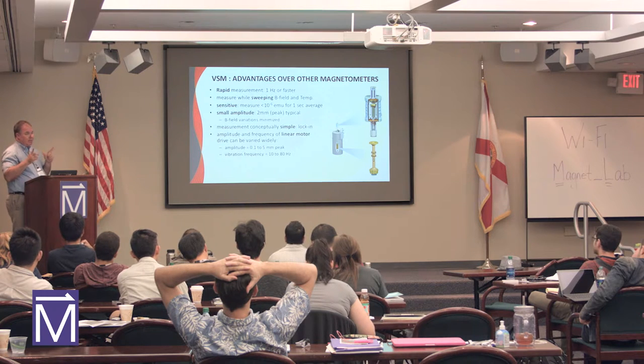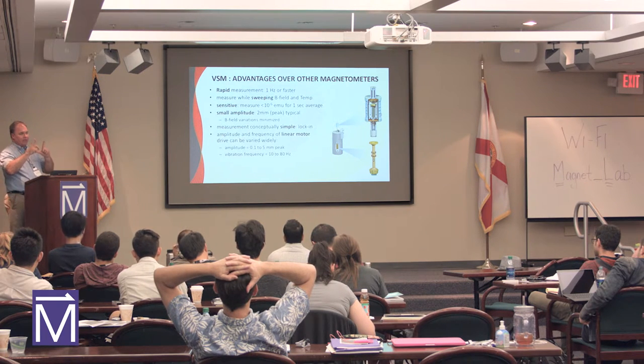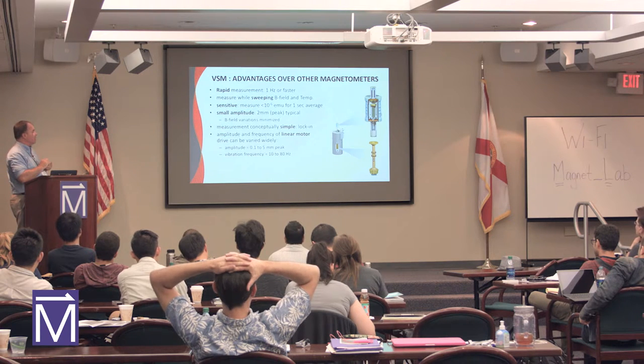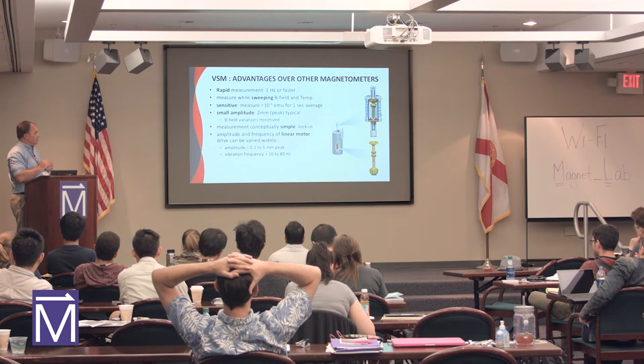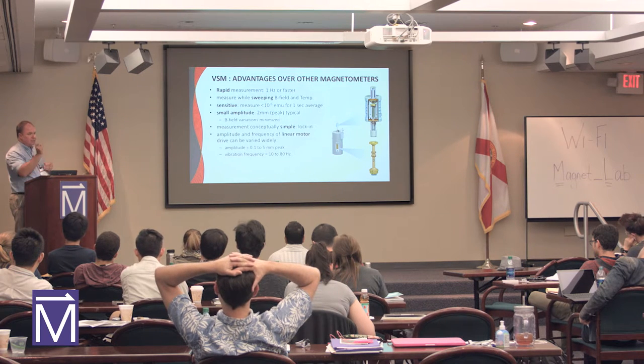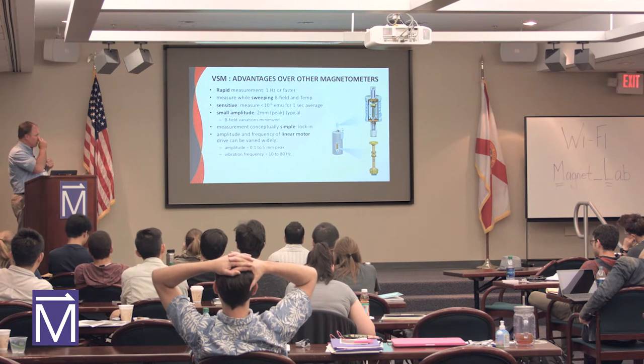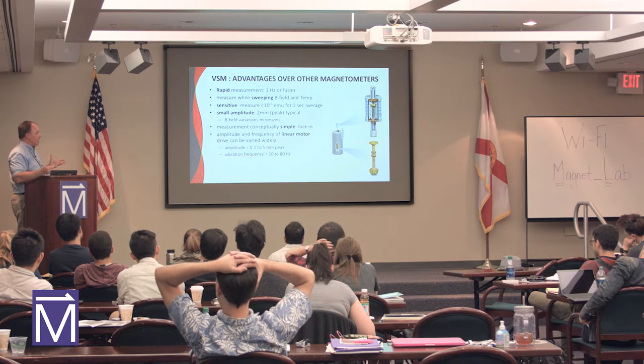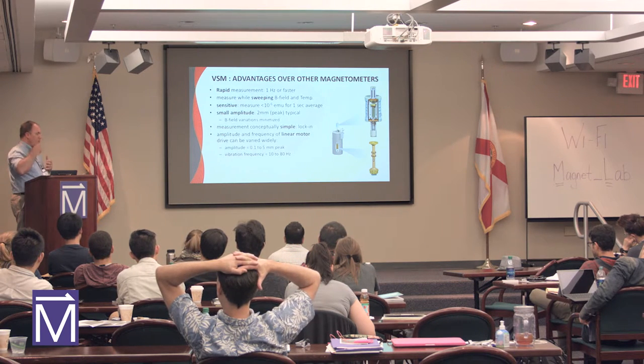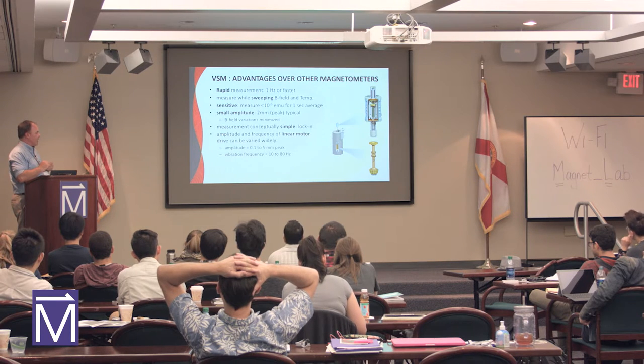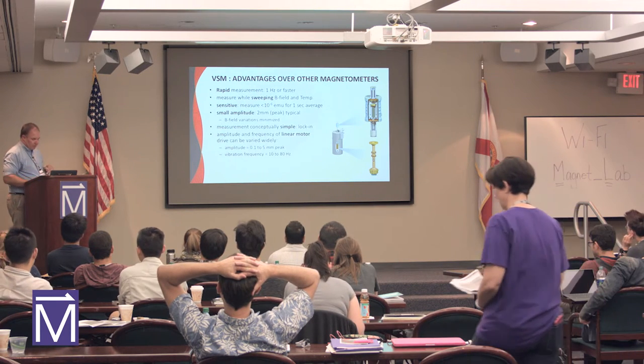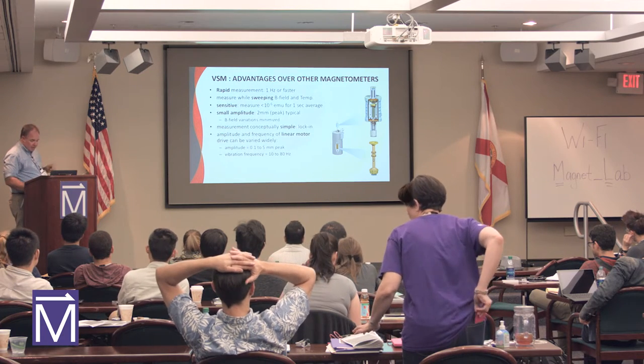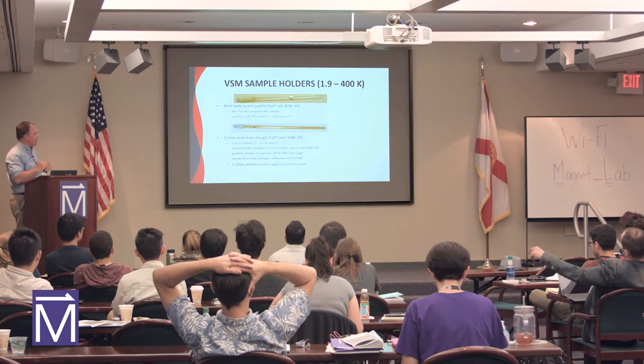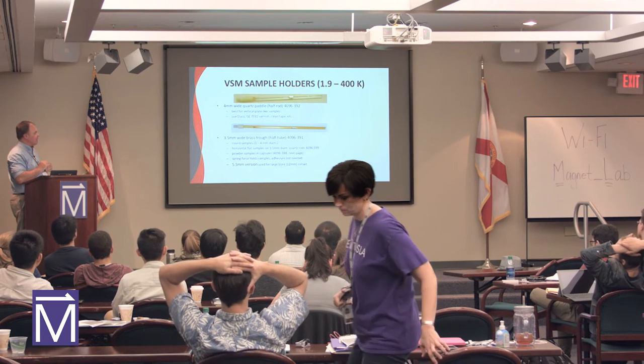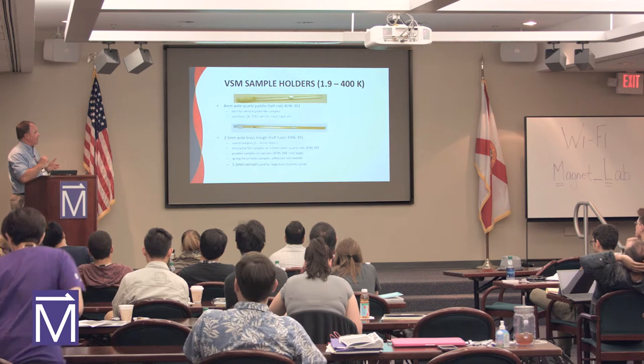So on the PPMS system, we have a nice plateau where the field's flat. It's about six centimeters where you've got a nice good uniformity in the field, and we're using a small portion of that. VSM's a lock-in technique, so we take the motion as a reference signal, and we can demodulate that reference signal. You can drive the motor from 10 to 80 hertz. It's about a 10 millimeter plateau on the homogeneous region of the magnet.